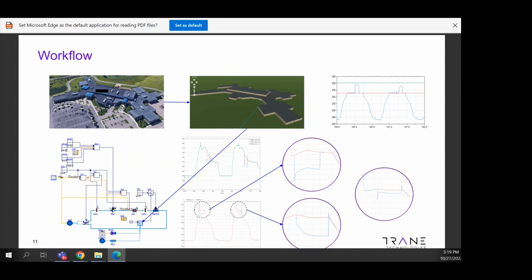The other strategy was showing that we had a shoot-up once the demand reduction period ended, so that is something we don't want. We can focus more on making sure that when the demand reduction period ends, we slowly get back to normal operating condition, and not suddenly. So this is just a recent example where we use this.